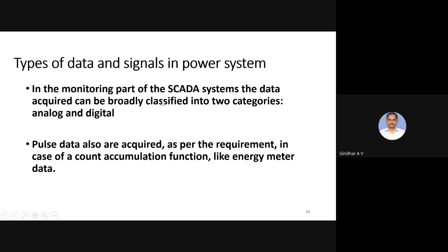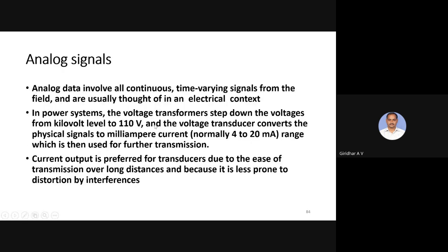So these are the various types of data and signals in the power system. Basically analog and digital data, and pulse data is also acquired, like for energy meter data and accumulation functions. These analog signals, like from voltage transformers, step down the voltage to the level of 110 volts, and there again voltage transducers convert this into the 4 to 20 milliampere standard; transducers will be used for that purpose.